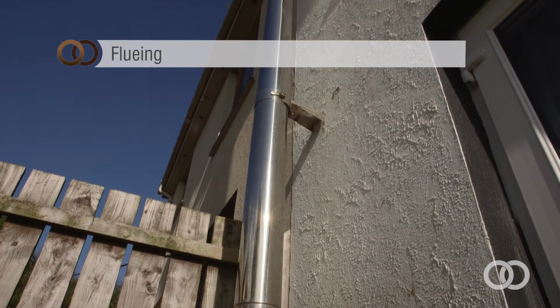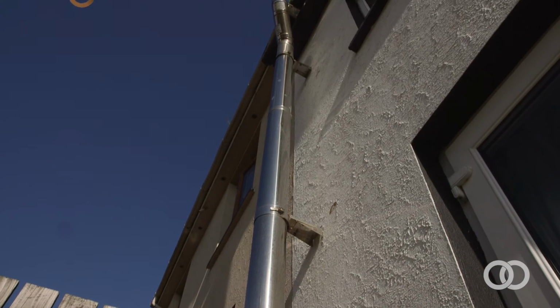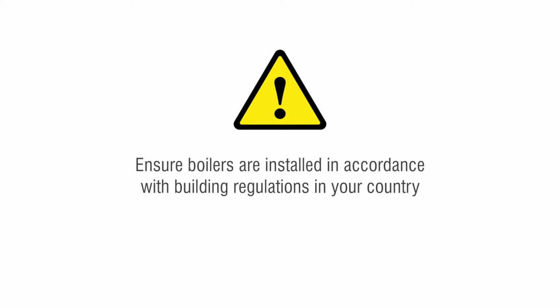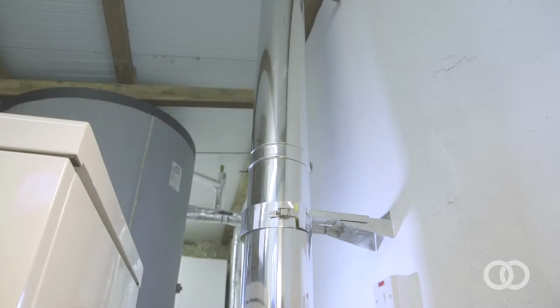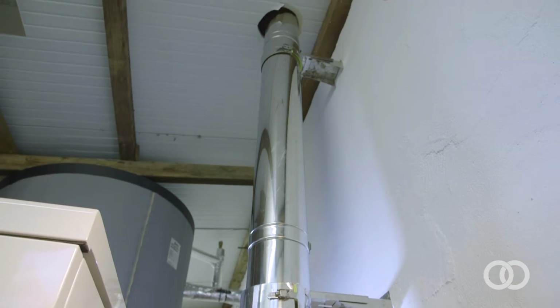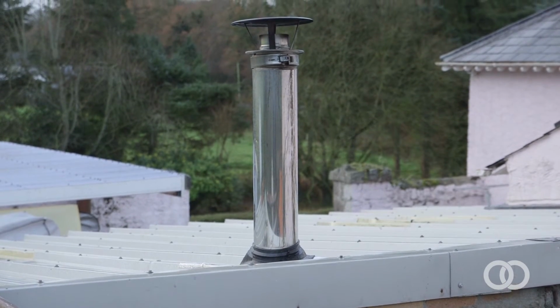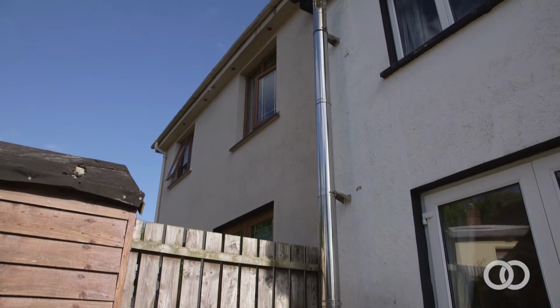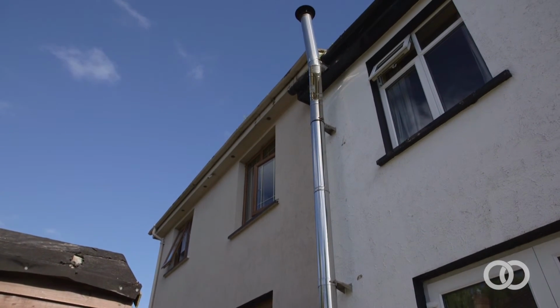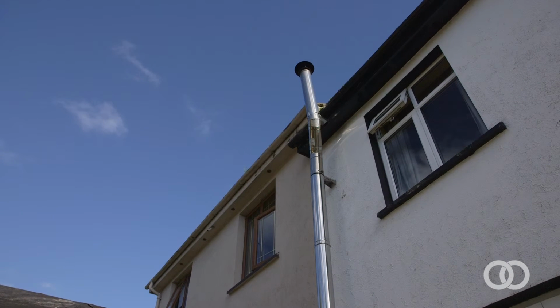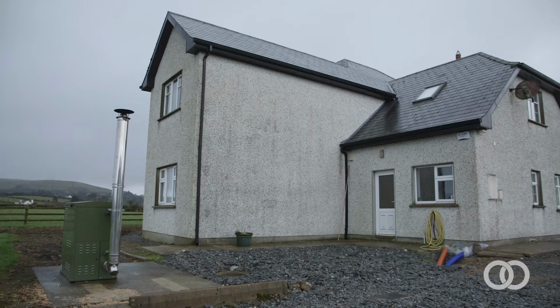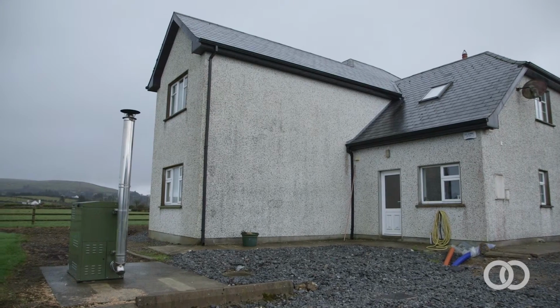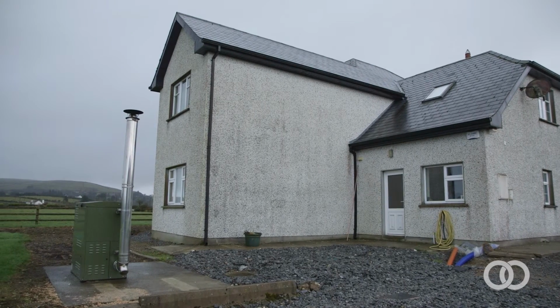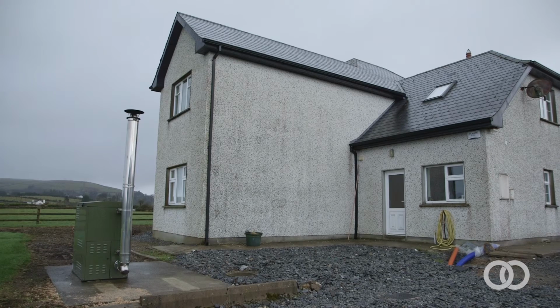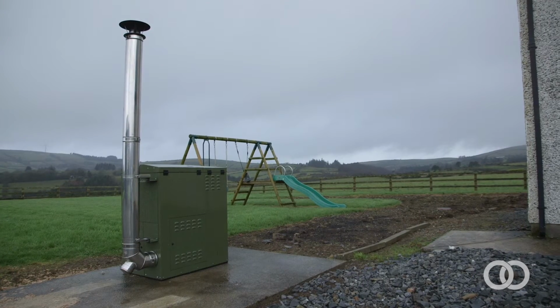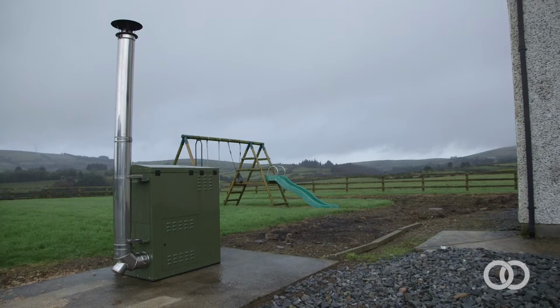Fluing. Fluing of the boiler is an important consideration. Ensure boilers are installed in accordance with the building regulations in your country. For internal boilers, the flue must terminate at least 1 metre above the eave of the roof. If the boiler is an external boiler, the flue must terminate at least 1 metre above the eave of the roof if located directly beside the building or within 3 metres of the building. Otherwise, if the external boiler is located further than 3 metres from the nearest building or tall structure, the standard shorter flue can be used provided the boiler can run satisfactorily and achieve a draft of 20 pascals.